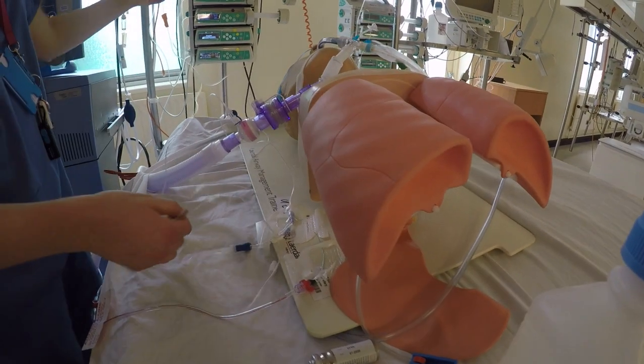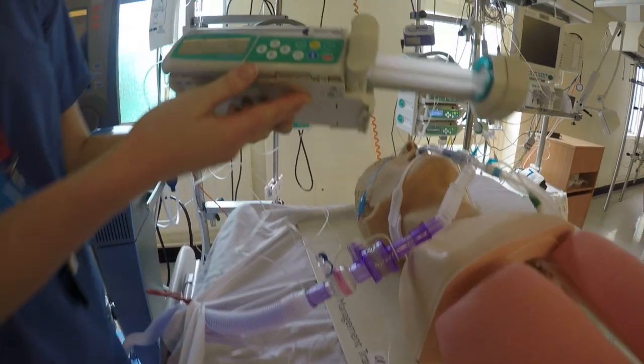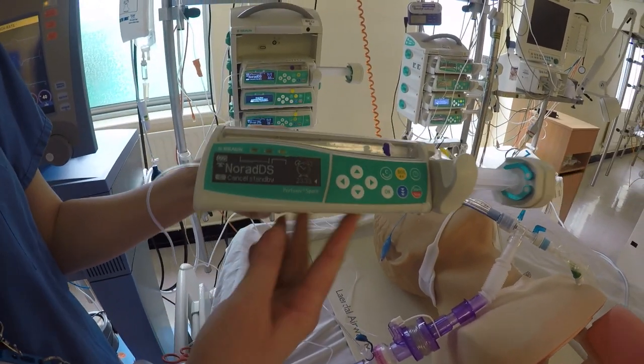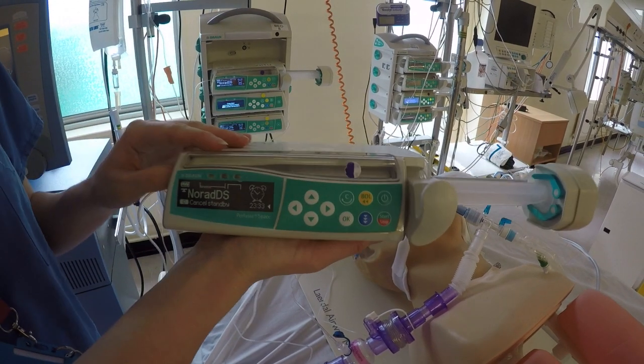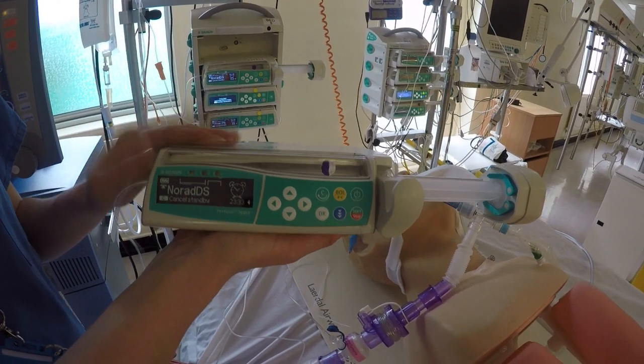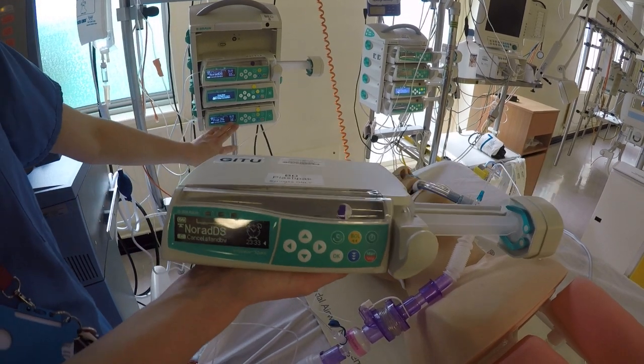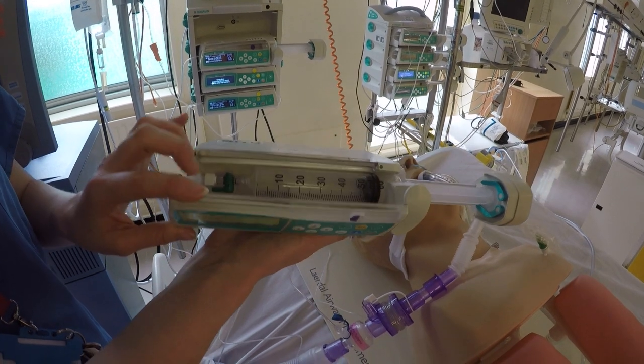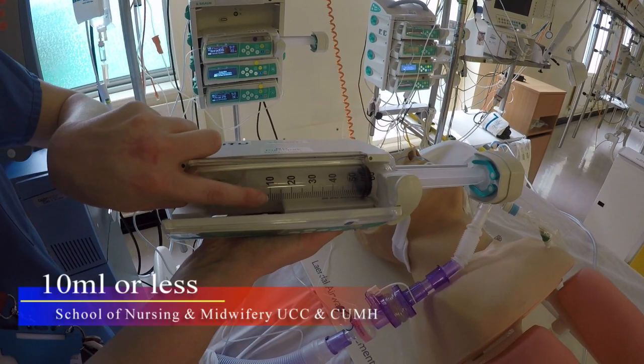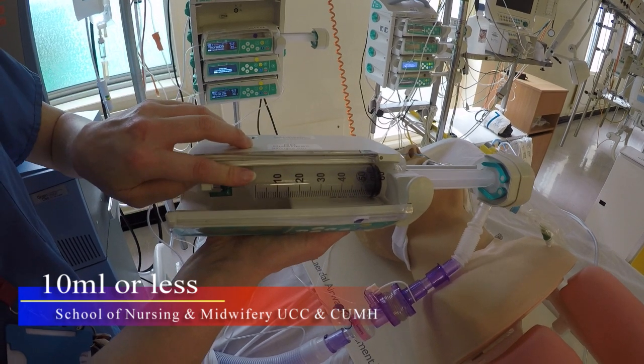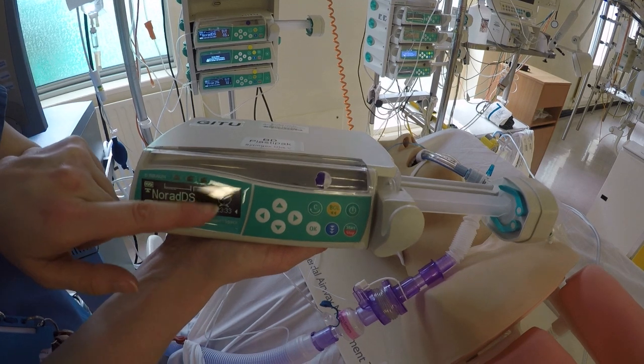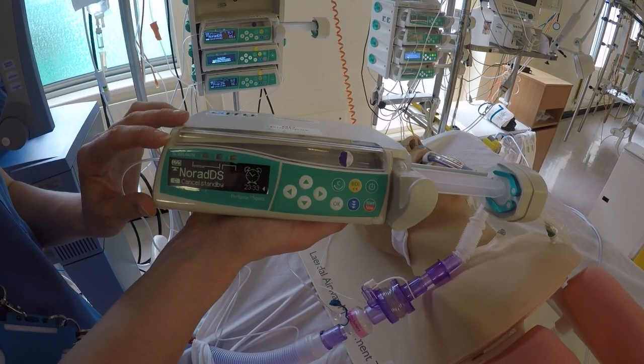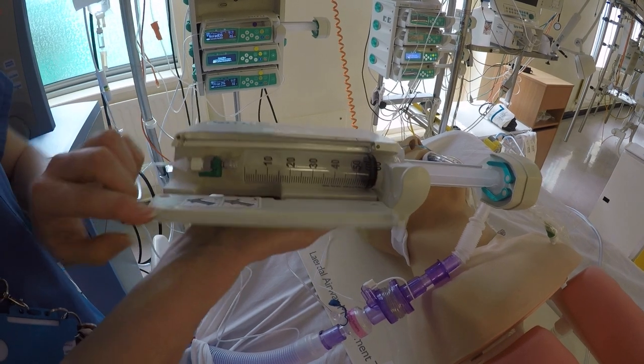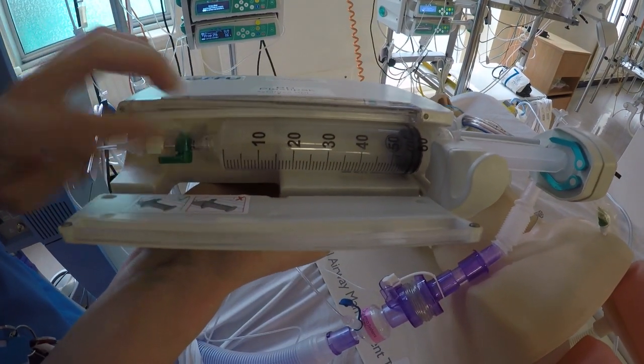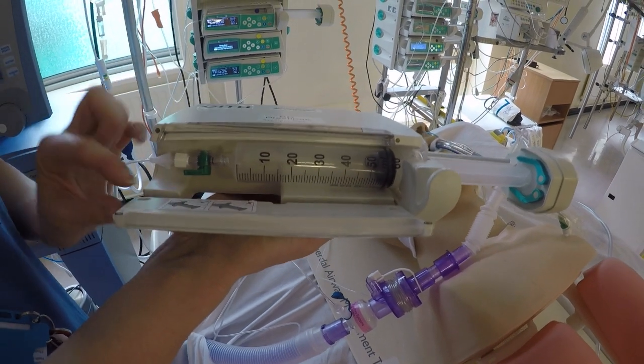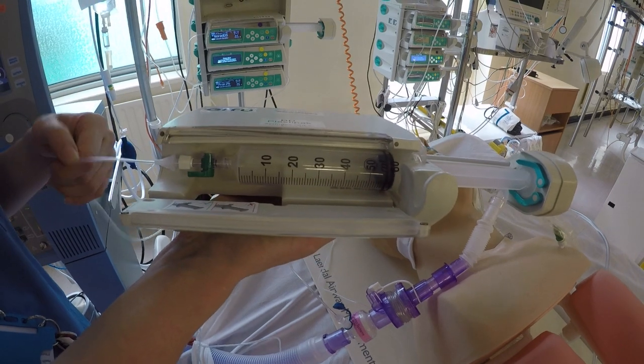The Braun pumps are what we use here. What we're saying to all staff is to be aware of the infusions. For example, there will be noradrenaline, which is an inotrope, and if there's propofol as well, which is sedation. You can flip down the cover here, so just let us know if that goes to 10 mils, so that we can prepare more medication, in case the machine hasn't been programmed with the volume, so that it doesn't alarm and say volume infused and turn off. For safety reasons, tell staff how many mils are left in the syringe, so that we can be vigilant, especially if we're supervising three or four patients, that the medication won't run out at any time.